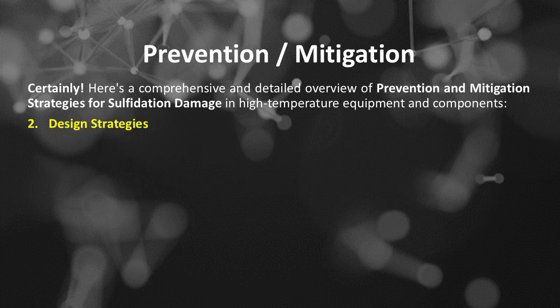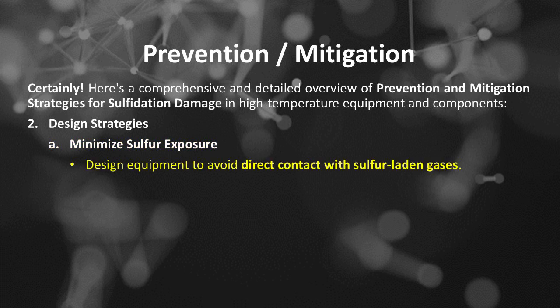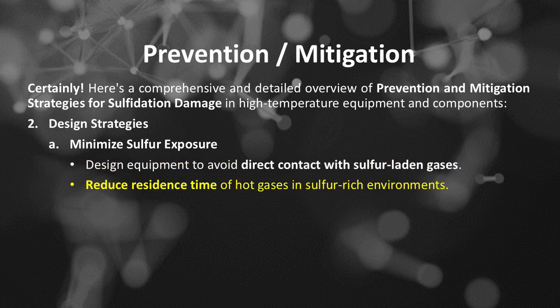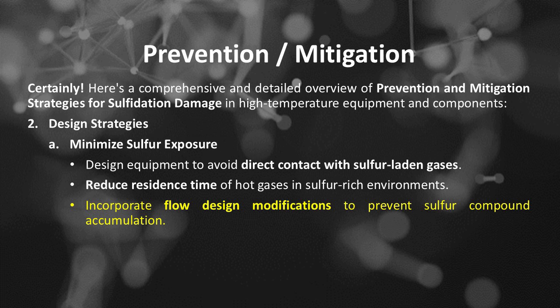Number 2 of prevention and mitigation strategies for sulfidation damage in high-temperature equipment and components is design strategies. Number A, minimize sulfur exposure. Design equipment to avoid direct contact with sulfur-laden gases. Reduce residence time of hot gases in sulfur-rich environments. Incorporate flow design modifications to prevent sulfur compound accumulation.